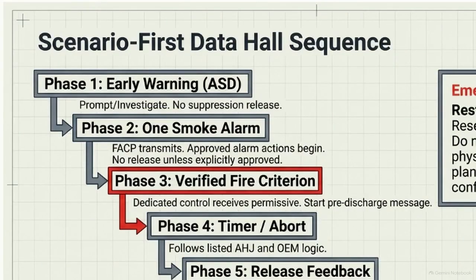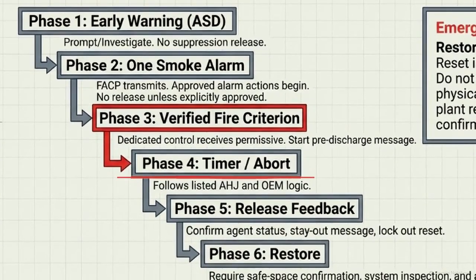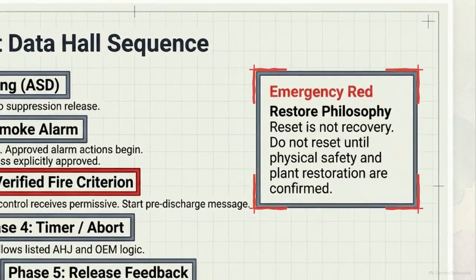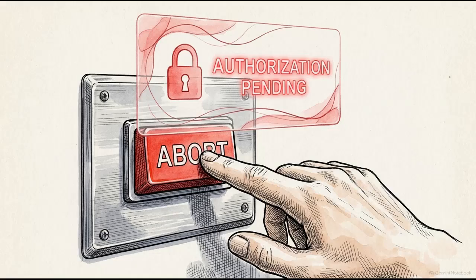This logic governs the phased data hall sequence. At phase 3, a single smoke alarm isn't enough. Explicit verified criteria must be met before starting the pre-discharge timer. Furthermore, the emergency red philosophy dictates physical safety must be confirmed before any system reset. This choreographed sequence prevents human panic from causing a premature and costly agent discharge.